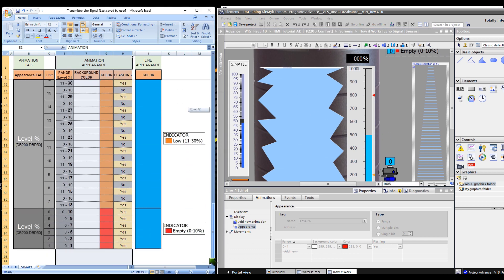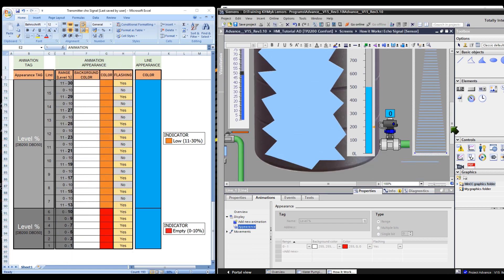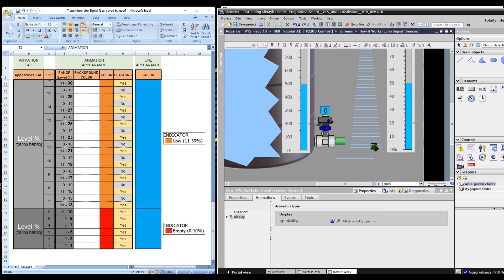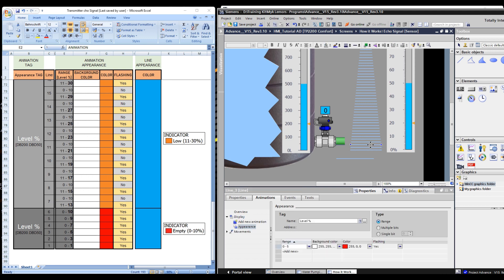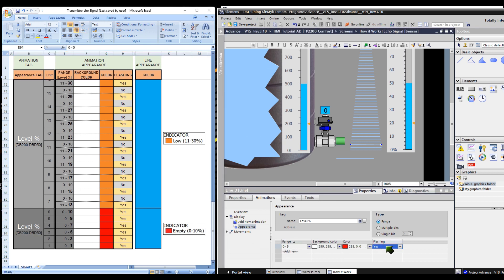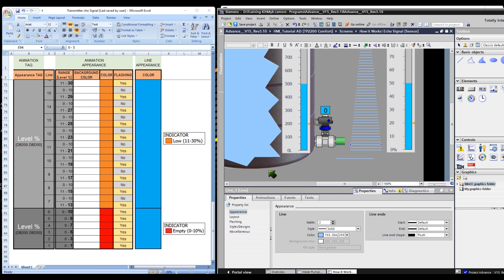Let's start from the bottom. In this object line, the animation appears when the level percentage is 0 to 5%. Flashing is confirmed within this range — the color of this line object flashes red and white. If this object line is outside this range, the object line will appear sky blue, matching the color of the water in the tank.